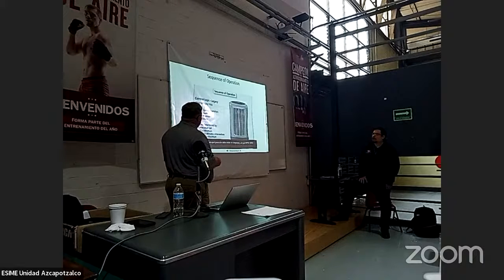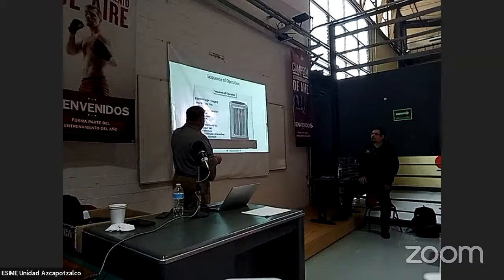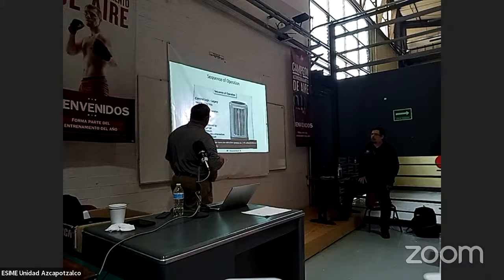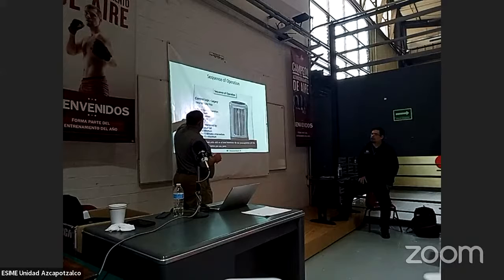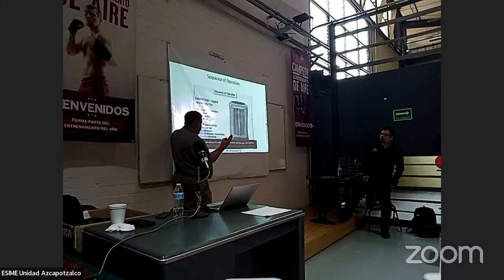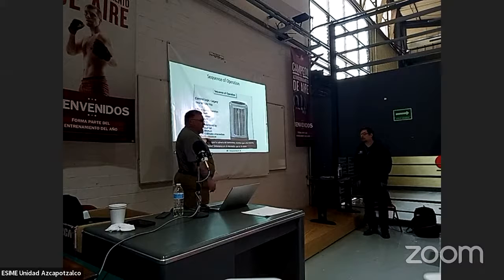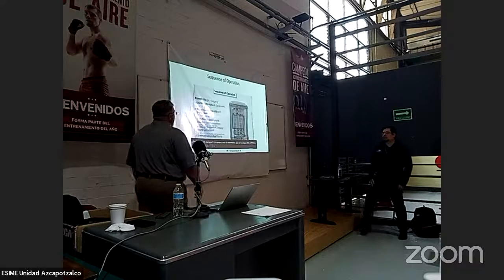Control logic: you get a 3-speed operation. This is called legacy. On the RP17s, 3-speed operation, intermediate, maximum speed determined by thermostat call. Y1 is minimum. Y1 plus 15 minutes, we're going to go to intermediate, stage 2, and Y1 and Y2 will go to maximum.